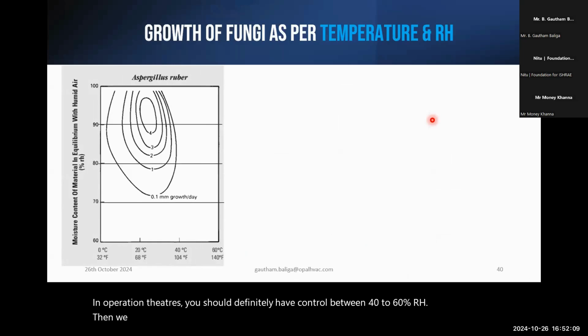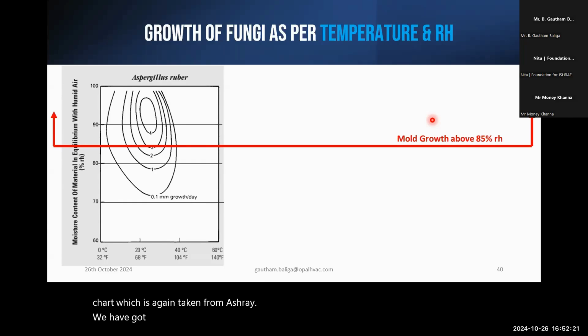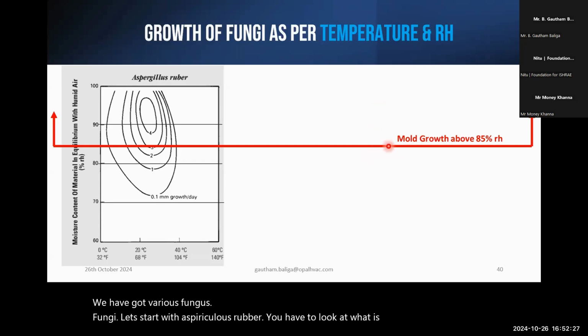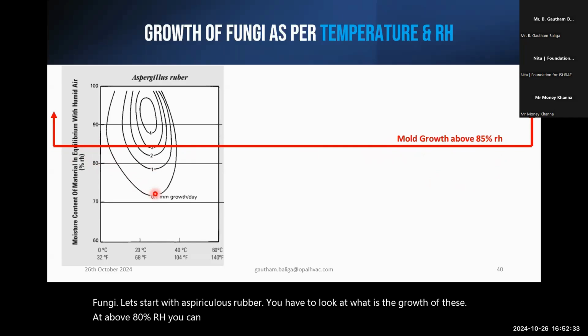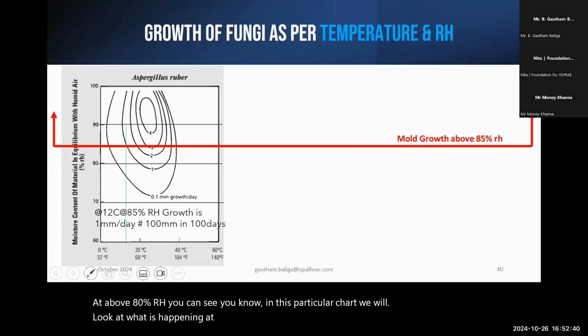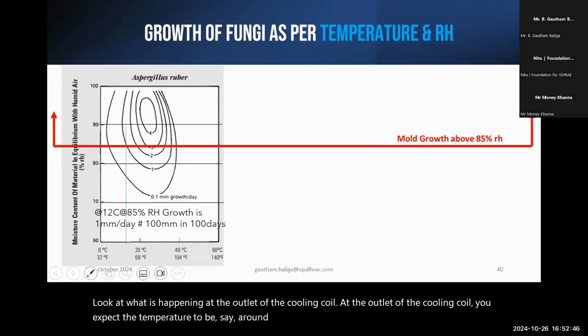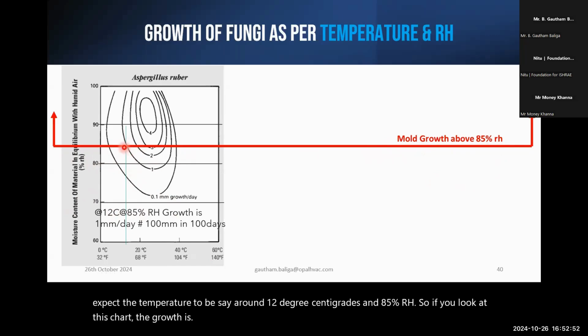Then we'll look at something about the growth of fungi as per temperature and RH. Here is a chart which is again taken from ASHRAE. See, we have got various fungi. Let's start with Aspergillus ruber. You have to look at what is the growth of these at above 80% RH. You can see, in this particular chart, we will look at what is happening at the outlet of the cooling coil. At the outlet of the cooling coil, you expect the temperature to be, say, around 12 degrees centigrade and 85% RH. So if you look at this chart, the growth is 1 mm per day.